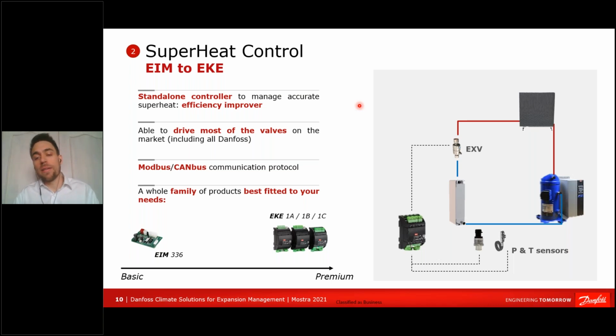If you switch to electronics, you need some kind of intelligence that gets the feedback from pressure and temperature sensors and is able to drive the valve, telling it to close or open regarding a certain superheat setting. This is what the EKE, or the superheat controller, is doing. This is a standalone solution that you plug on the main controller, but basically it can drive the valve and do all the work of translating the pressure and temperature signals into closing and opening signals for the valve. It's connected through Modbus or CAN bus to the main controller, and it comes in different versions.